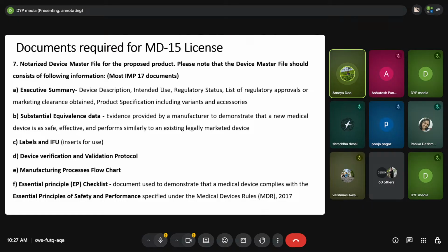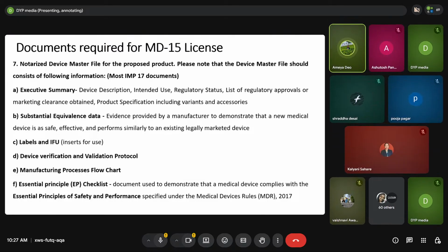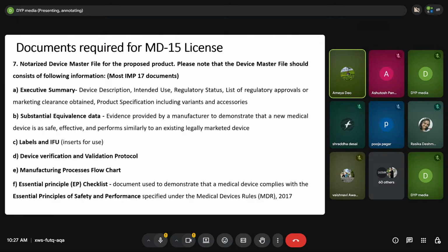which is the evidence provided by the manufacturer that the device is safe, effective, and performs similarly to legally marketed devices. The labels and IFU, that is instructions for use, also need to be submitted to understand the compatibility of the product. Then device verification and validation protocols. Then the manufacturing process flowchart, that is how the device is manufactured, the stepwise procedure that you need to understand. Then the essential principle checklist. Again, this is a document provided by the CDSCO, in a format which the manufacturer needs to fill and sign.